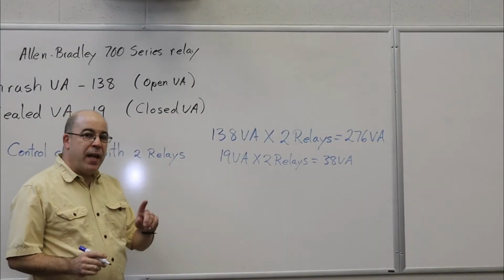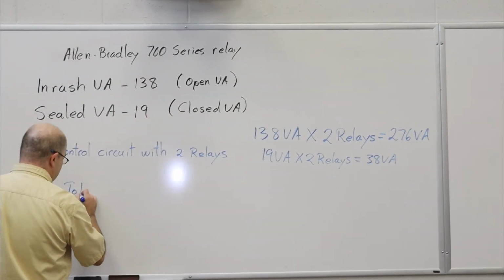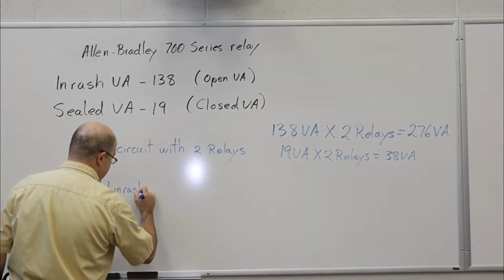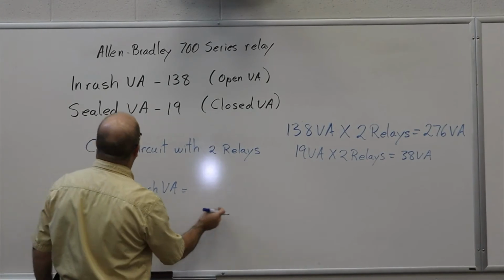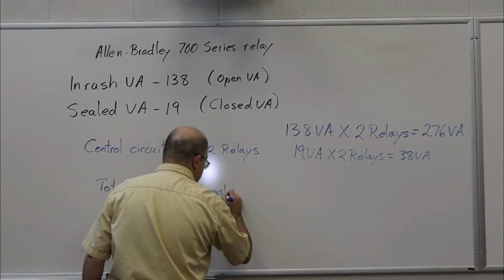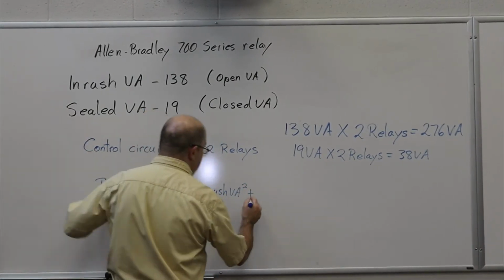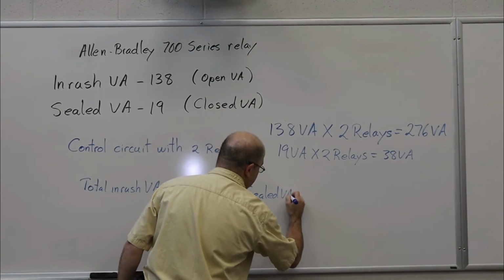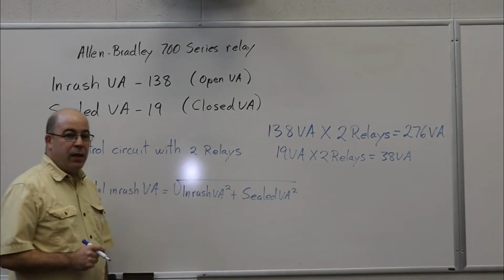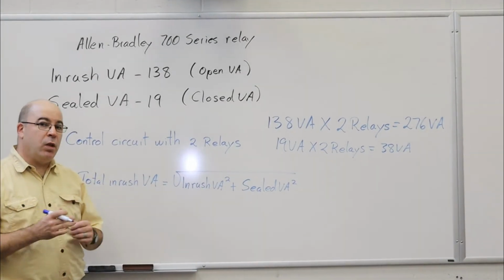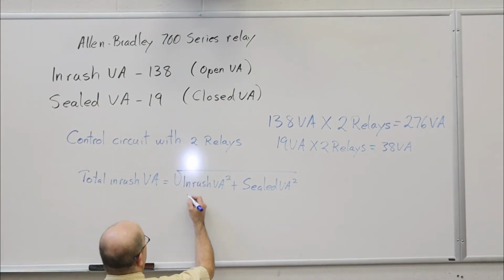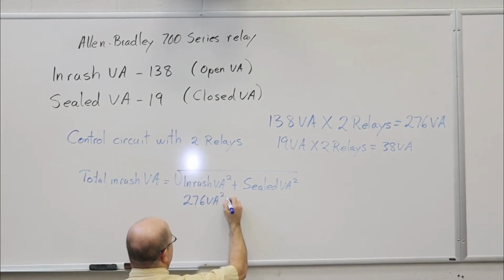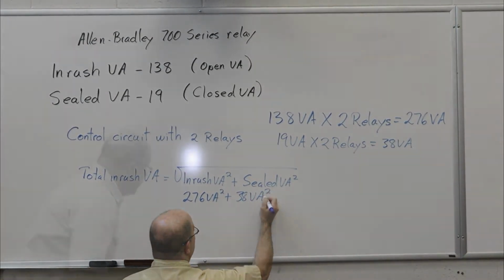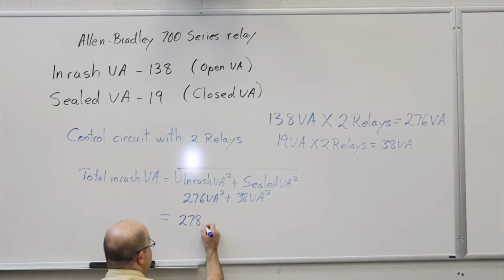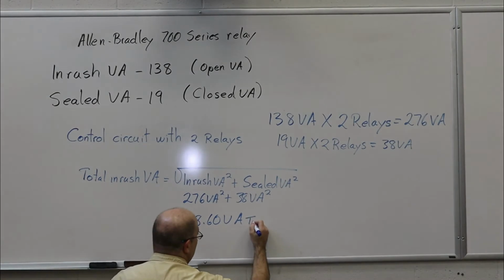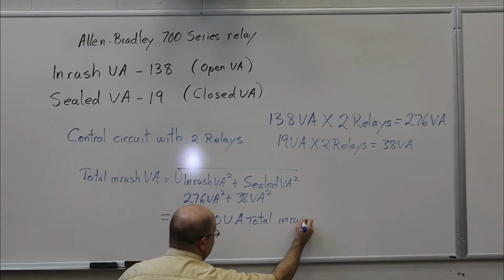Now, in the formula provided to us, your total inrush VA is equal to the square root of your inrush VA squared plus your sealed VA squared. So we're going to input our values, and we're going to proceed to calculating that. In this case, 276 VA squared plus 38 VA squared, and we get 278.60 VA total inrush.